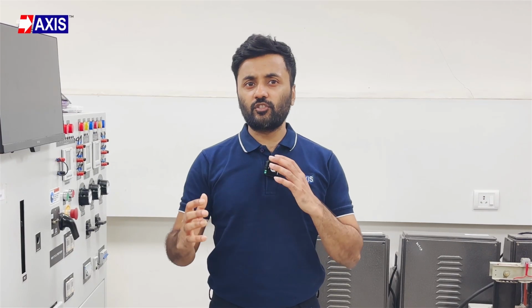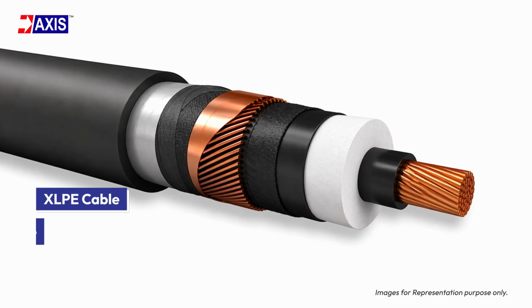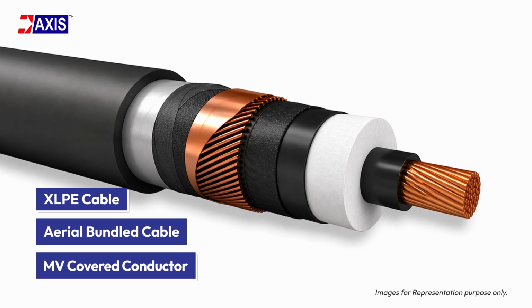The performance of your cable system does not depend only on the cable. Joints and terminations are the most stressed points in the installation. If you select the jointing or termination kit incorrectly, it will lead to overheating or insulation failure. Therefore, before selecting them, you must check a few details about your cable and the installation. First of all, the type of cable. You must first identify the type of cable you're working with. Is it an XLP cable, aerial bundle cable, or a medium voltage covered conductor?